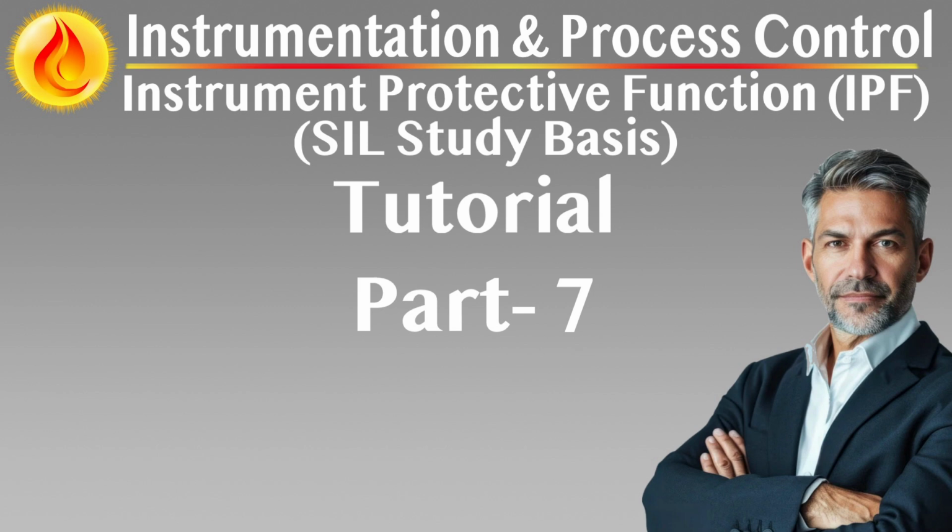Interface with emergency shutdown, ESD, and fire and gas systems, FGS. Fire and gas IPFs must be fully integrated into the site's ESD hierarchy, triggering partial or full shutdowns based on detection logic. Responses may include alarm activation, personnel alerts, unit isolation, blowdown, or emergency power cutoff.